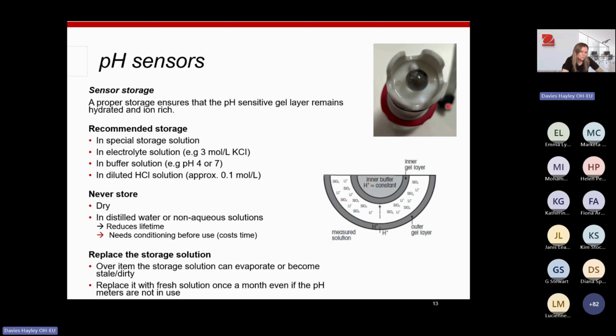You can use that, or you can just use an electrolyte solution, 3 molar KCl. That is the electrolyte used in a lot of the pH electrodes. You can make up your own solutions of 3 molar KCl. If you don't have any 3 molar KCl, you can store it in a buffer solution, so you can use a pH 4 or a pH 7, and you can store your pH probe in those. Or in a diluted HCl solution, hydrochloric, about 0.1 molar. Any of those you can store your electrodes in.